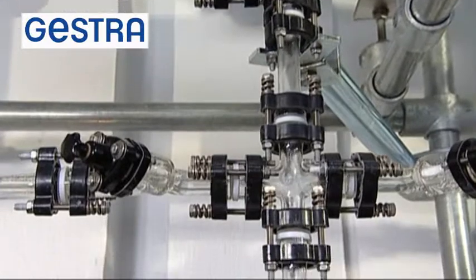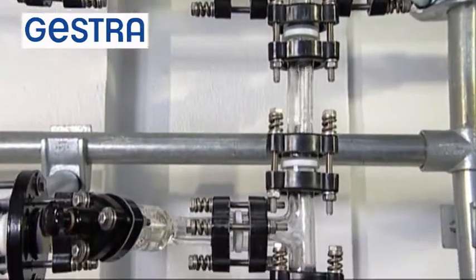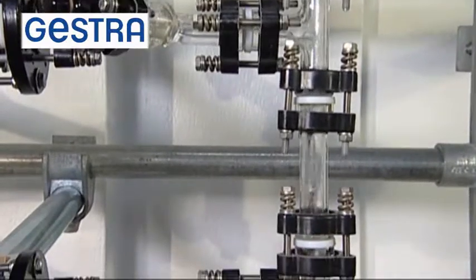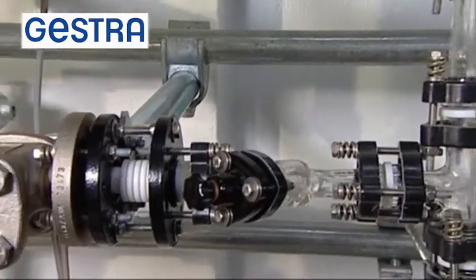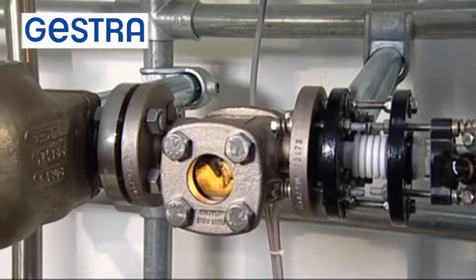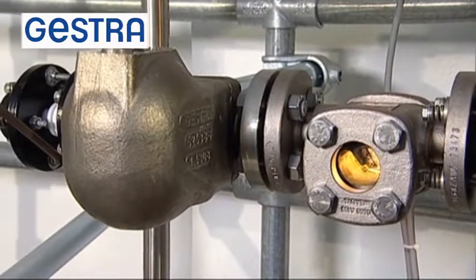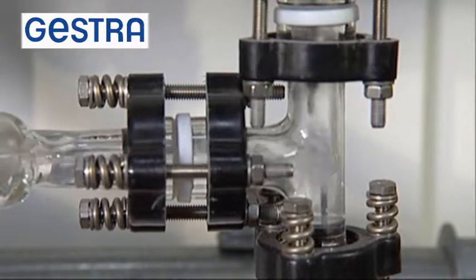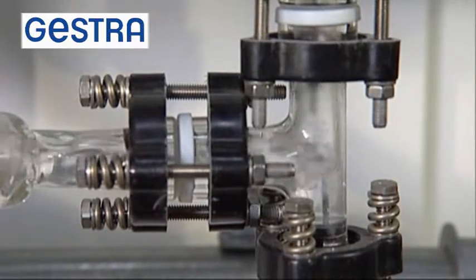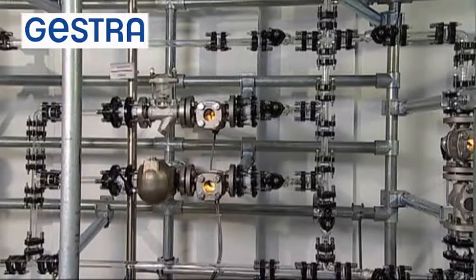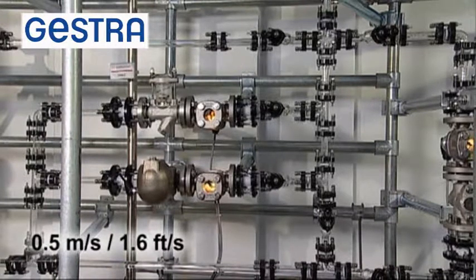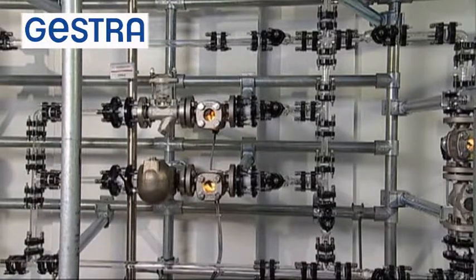With this arrangement, the float trap is installed correctly. It's located below the heat exchanger. The condensate can flow vertically downwards through gravity. Steam bubbles can rise up freely and return to the heat exchanger. The nominal size of the condensate line should not be chosen too small, so that the calculated flow velocity of 0.5 meters per second is not exceeded. Built-in strainers should be cleaned at regular intervals to prevent an unwanted pressure loss.